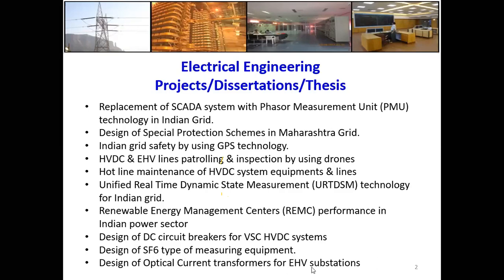Then in EHV substations, for measurement equipment like PTs, CVTs, and CTs, you can go for new technology, that is optical current transformers or transducers. You can use optical current transducers for the measurement of voltage and particularly currents. So you can work on these optical current transformers for EHV substations.